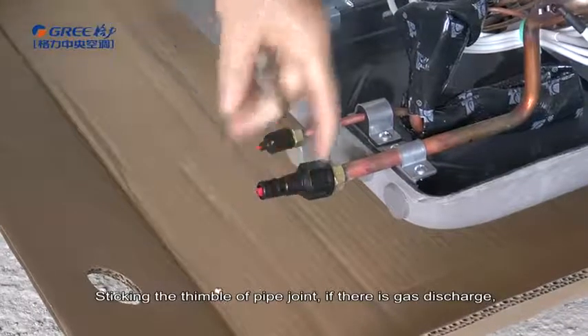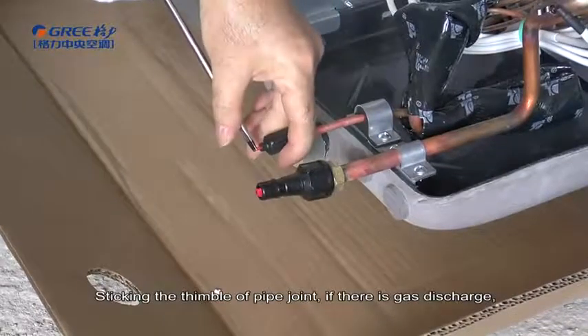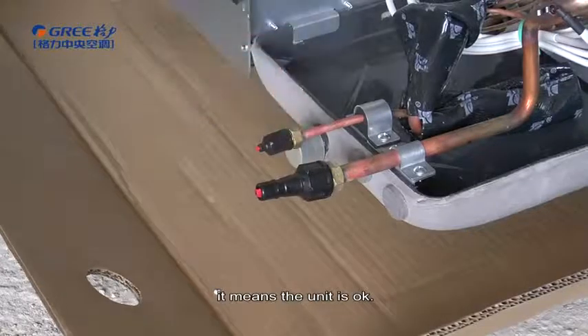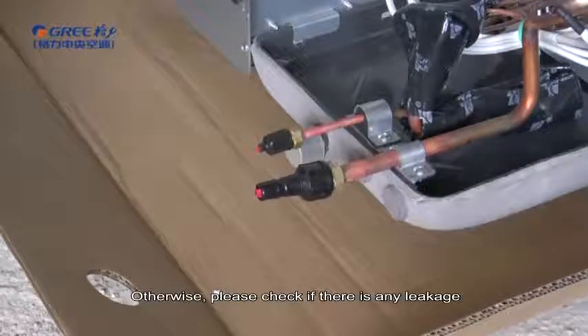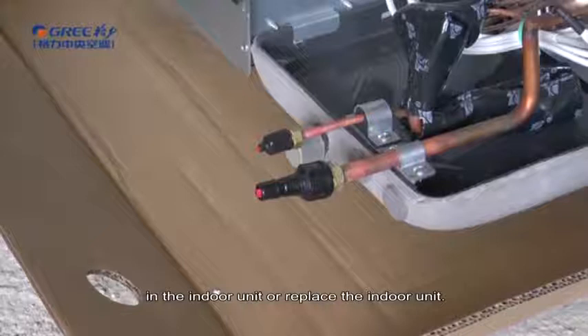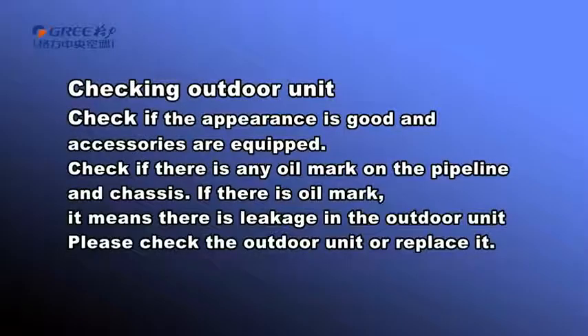Sticking the thimble of pipe joint. If there is gas discharge, it means that the unit is okay. Otherwise, please check if there is any leakage in the indoor unit or replace the indoor unit. Checking outdoor unit. Check if the appearance is good and accessories are equipped. Check if there is any oil mark on the pipeline and chassis. If there is oil mark, it means there is leakage in the outdoor unit. Please check the outdoor unit or replace it.